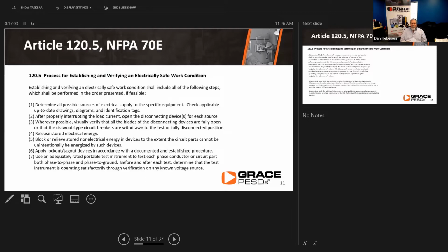And you really want to make sure that everybody is up to date with the equipment, has gone through and understands each of the job tasks that are appropriate. And at the very end, you're going to use an adequately rated portable test instrument to test each phase conductor or circuit part, both phase to phase and phase to ground. And before and after each test, determine that the test instrument is operating satisfactorily through the verification process.